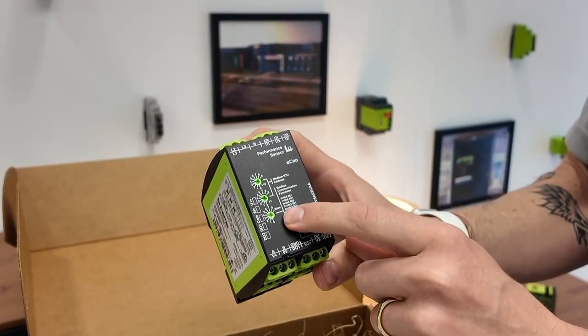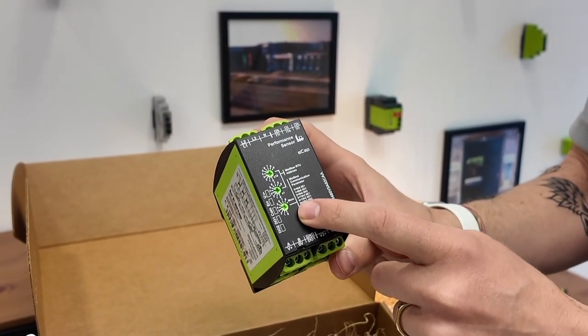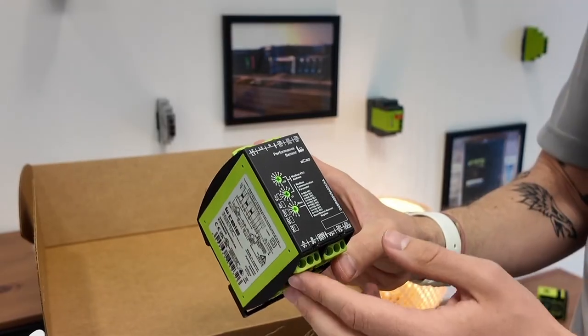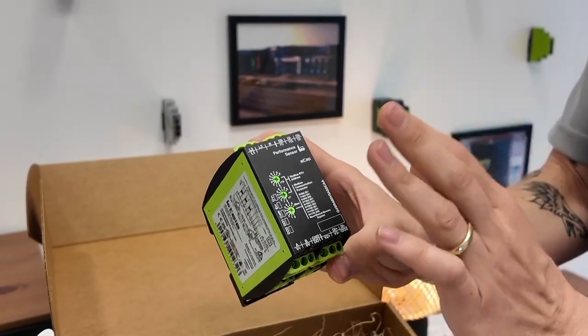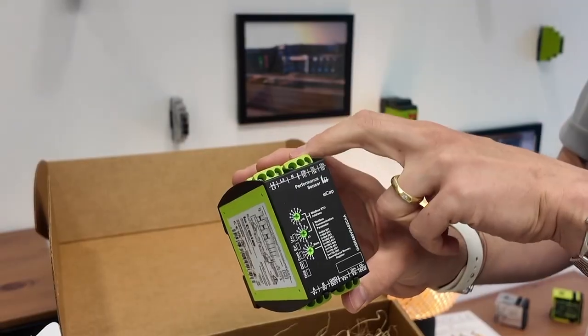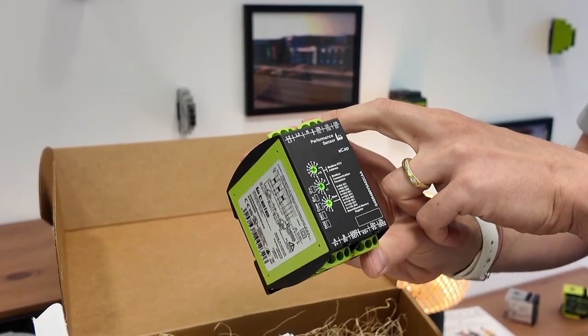Those three dials enable you to set the Modbus address, so you don't have to power the unit up and connect it to software to get up and running. All you need is a screwdriver, connect the wires for voltage and current, and off you go.